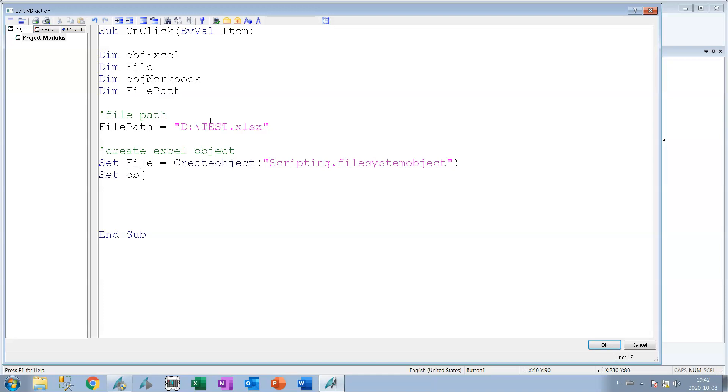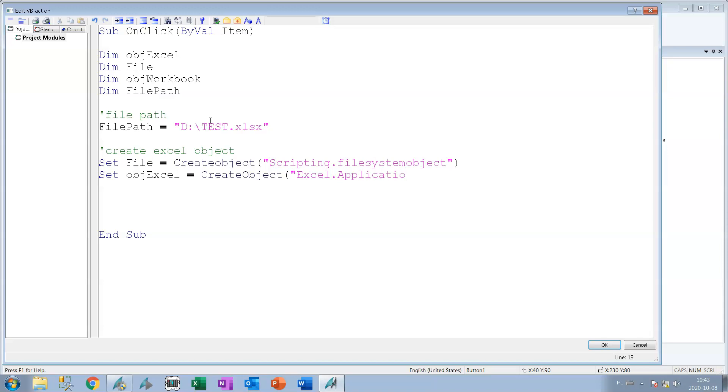The next object is the Excel object and this Excel object will be created by this file system object. Before you make this Excel.Application you need to have Excel on your WinCC application because you need to have the library for the Excel application in your system. If you don't have it you can't use this library in your Visual Basic Script editor.